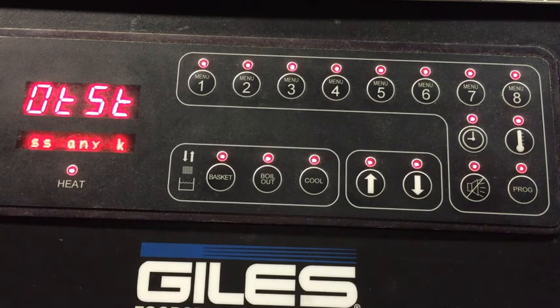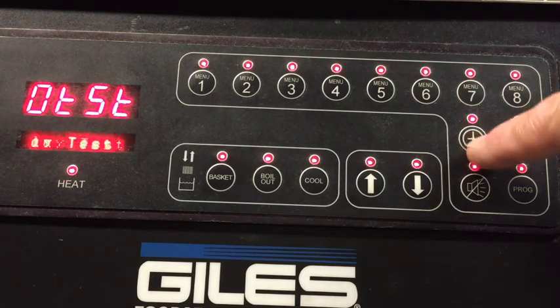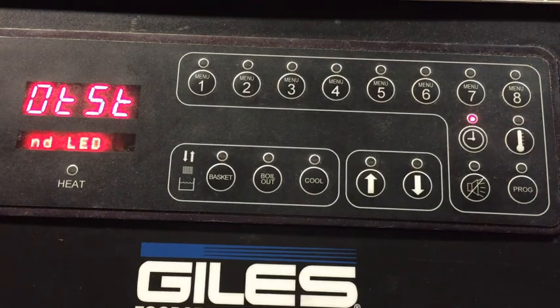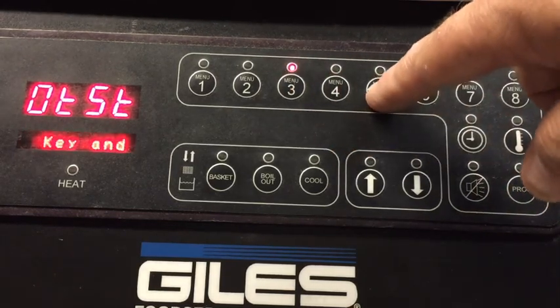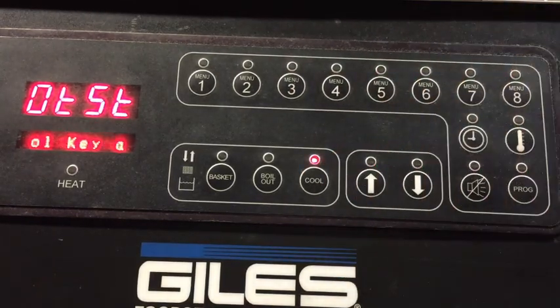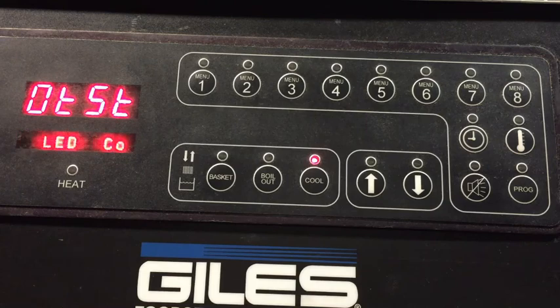When it's in this one, it says you can press any key. So if we press the clock, you'll see that it says clock key and the LED is lit. The alarm reset, same thing. 3, 5, 7, doesn't matter. Any of the keys, and it'll tell you which one they were, so that you'll know that the computer is actually seeing the key that gets pressed. All right? A very, very important one to remember, especially as units get a little age on them. 3, 4 years out. Sometimes they last much longer than that, but anytime after 3 to 4 years, you might see that. And we do still have the keypads available, so you can purchase those for replacement.